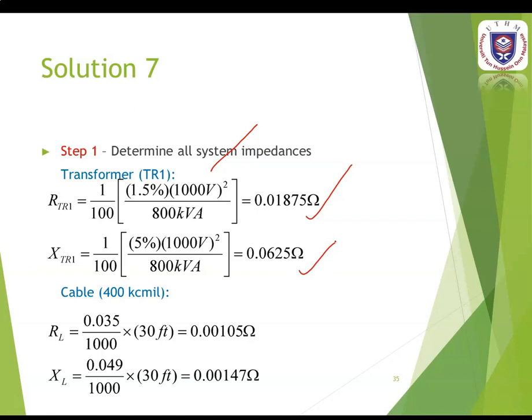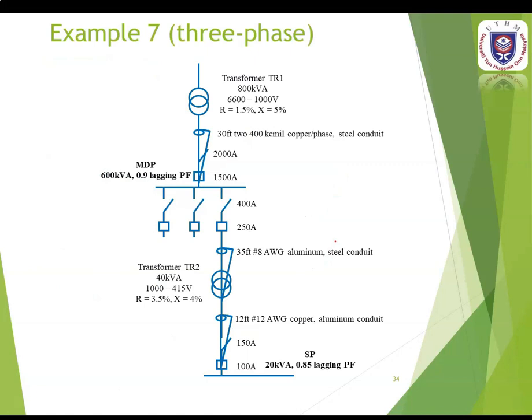For the cable 400 kcmil, you have to do the analysis starting from the source. You refer to this diagram: transformer, then go to the 400 kcmil, then the 8 AWG, then the transformer to 12 AWG. For the cable 400 kcmil, you refer to the 600 volt table. For the three-phase equation there is no factor of 2.